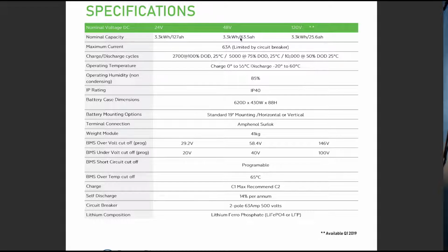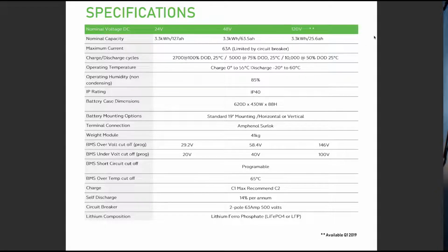Now, with the life cells, they've got a 100% capacity of 3.3, looking at the data sheet. The maximum depth of discharge there, and I'll cut back to it so you can see that spreadsheet, determines the lifespan of the battery, as it does with most cells. If we're going to take 100% out of those cells, we'll only get 2,700 cycles, which if you think of a daily cycled system is, I don't know, about 8 years or so. If you're taking 75% out, you're getting 5,000 cycles. So that's more like about 15 years or so.